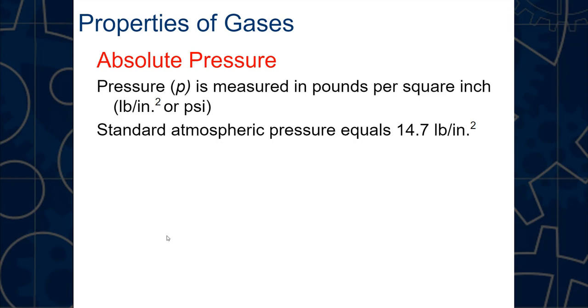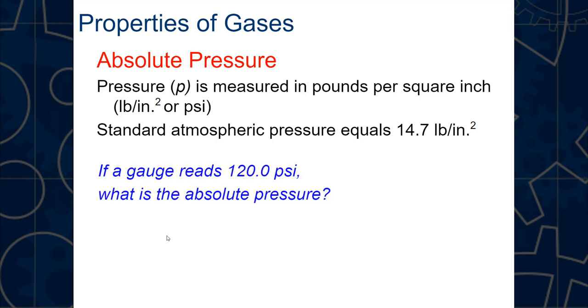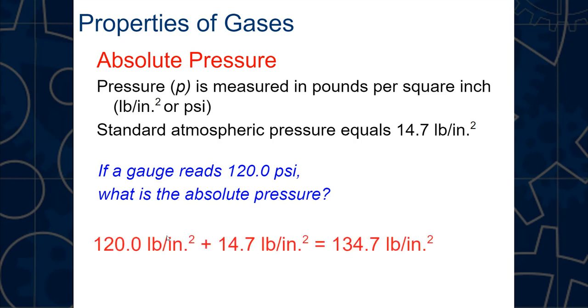Standard atmospheric pressure is 14.7 psi, which we add to whatever we read directly off the device to get absolute pressure. For example, if the gauge reads 120 psi, you add 120.0 psi plus 14.7 psi to get 134.7 psi absolute pressure.